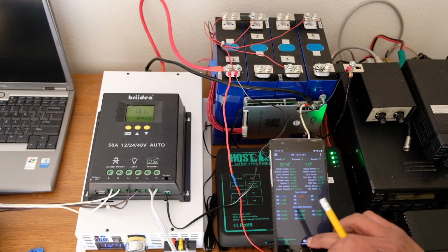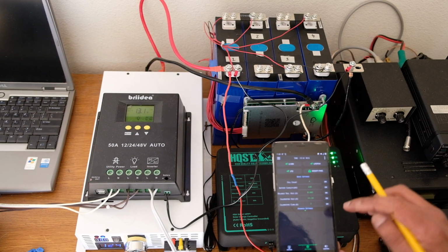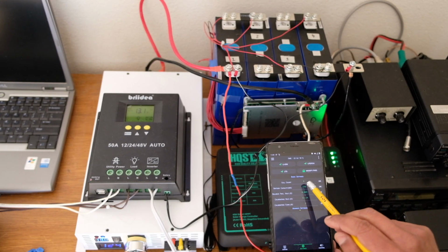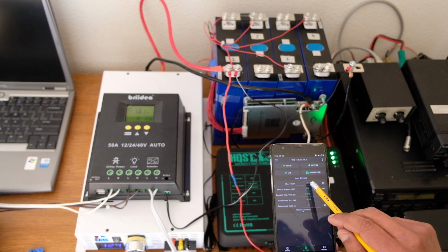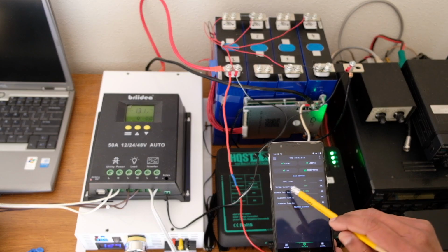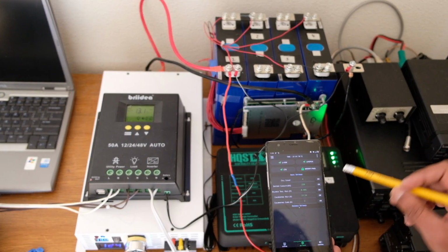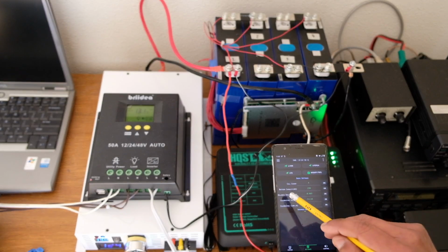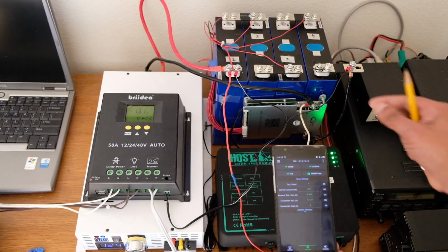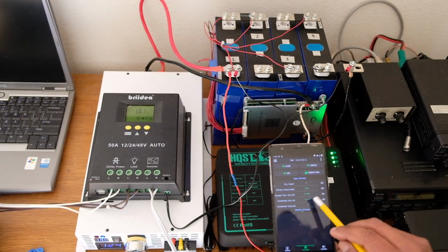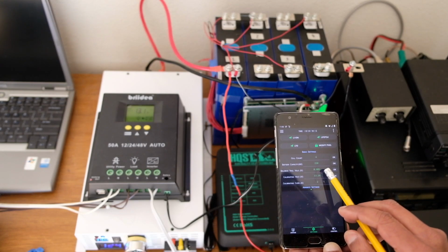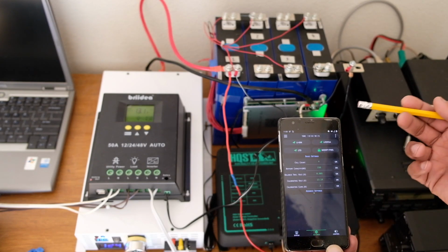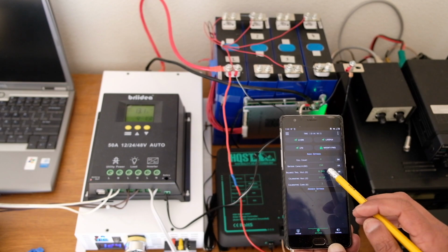You've got to first do some setup, which is to change the number of cells to 4 in this case, and also the battery capacity in ampere hours, and you can also change the balance voltage - that is, whenever the cells are mismatched by greater than 5 millivolts in this case, it will start balancing. It's got active balancing, which is nice, up to 2 amps of current.